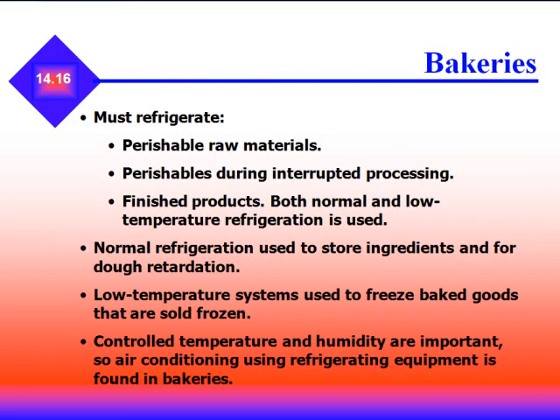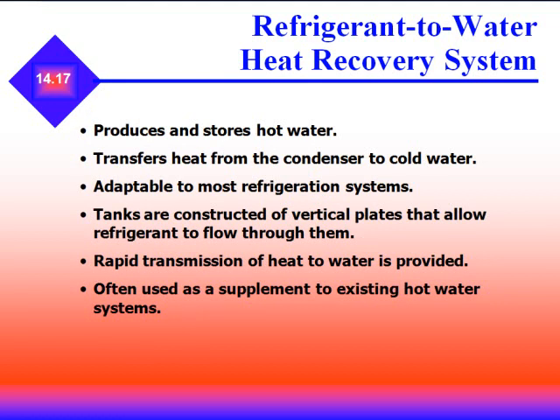Bakeries must refrigerate all perishable raw materials, perishables during interrupted processing, and finished products. Both normal and low temperature refrigeration are used. Normal refrigeration stores ingredients and is used for dough retardation; low temperature systems freeze baked goods sold frozen. Controlled temperature and humidity is important, so air conditioning using refrigeration equipment is found in bakeries. Heat recovery is also accomplished by refrigerant-to-water systems, which produce and store hot water, transfer heat from the condenser to cold water, and are adaptable to most refrigerant systems.